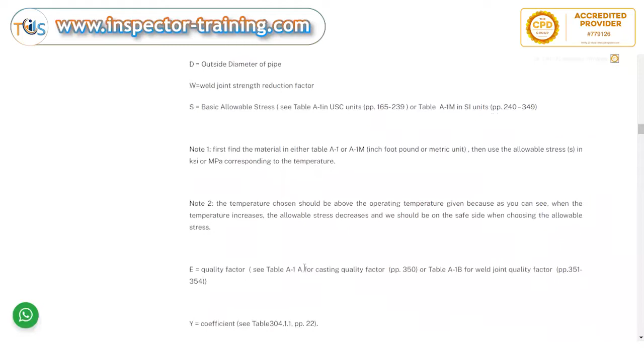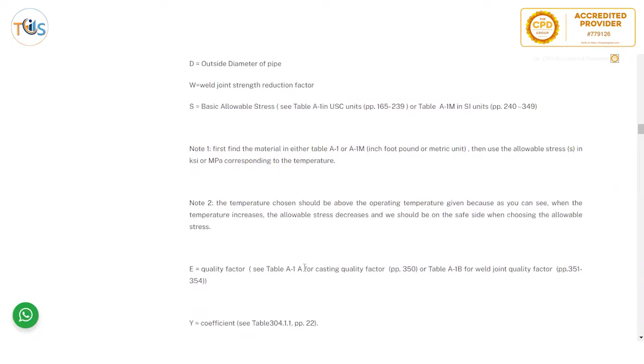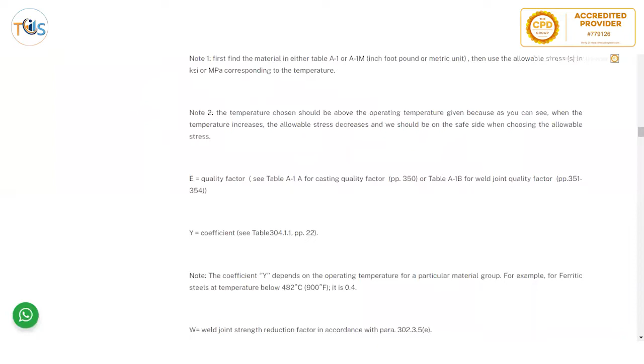The temperature chosen should be above the operating temperature given, because as you can see, when the temperature increases, the allowable stress decreases, and we should be on the safe side when choosing the allowable stress. So you should always select the temperature above that. If they're telling, for example, temperature is 130, you go for 150 here, because you should be on the safe side. You round it up to the higher number.